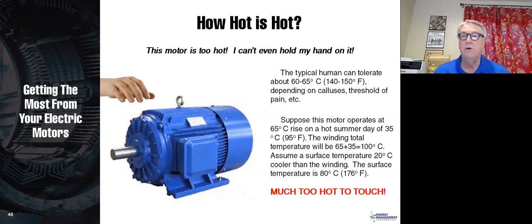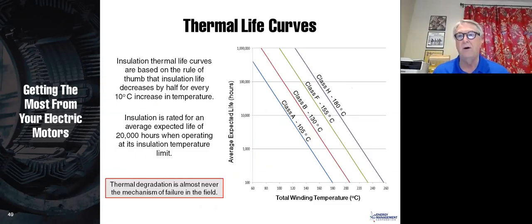And we just showed you that you can only tolerate 60 to 65. So my point is, if you can keep your hand on the outside of the motor for 3 seconds, in a totally enclosed fan-cooled motor or in a rolled steel frame type motor, the motor is not too hot. If you can't keep your hand there, it might still not be too hot, but that's the point at which we need to measure the temperature and do a little bit of calculation. A little harder than just sticking your hand on a motor.